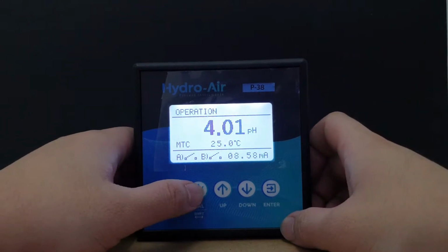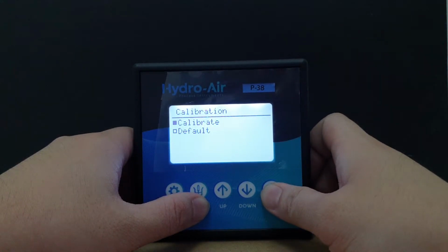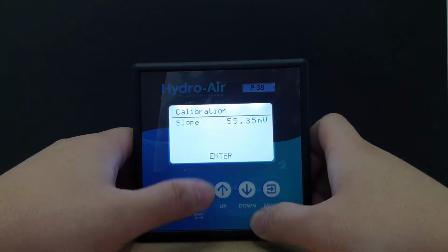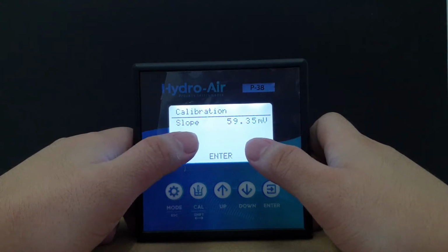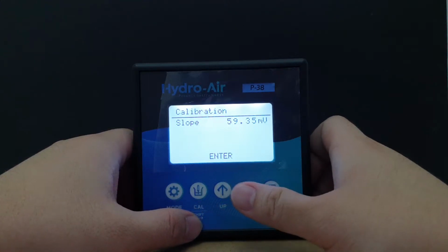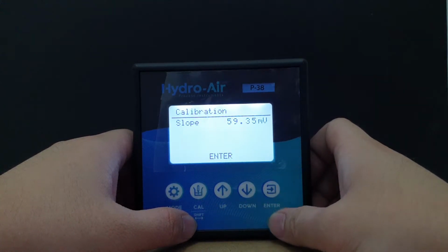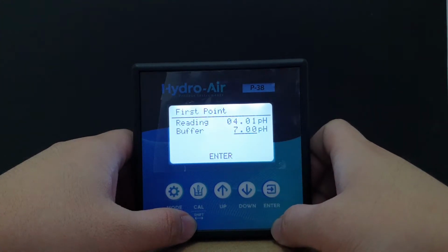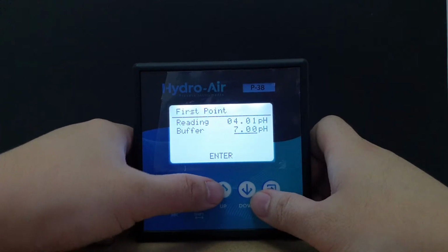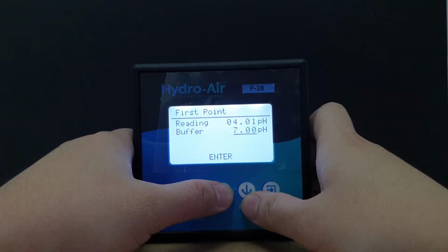All you have to do is press Cal once and press enter on calibrate. And here you can see that there's a calibration page where it shows you the slope for the previous calibration. Press enter. And for the first point, you have two buffer selections.